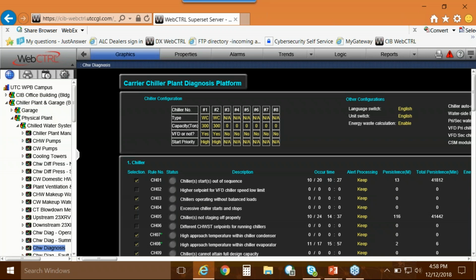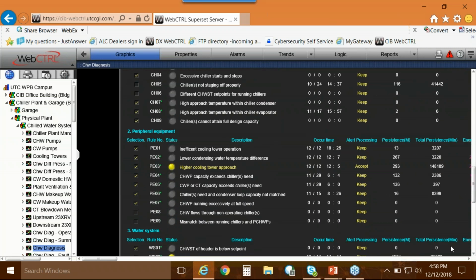We are bench testing a diagnostic, fault detection and diagnostic platform where you're just seeing a portion of the screen. We've logged in 2 300-ton capacity chillers. We've got 9 FDD rules—chillers starting out of sequence, high set point on the VFD, it's not slowing down enough, the chillers are not running on a balanced load, on and on. It's a saleable product. And there we have a high cooling tower approach alert, and it's been there since the building opened. We still haven't figured out what's wrong in the algorithm yet, but either we've got too much sensitivity or we're not measuring the right stuff.